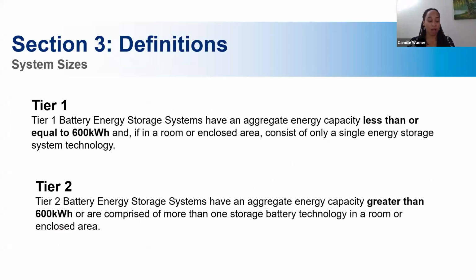For tier 1, let's jump into definitions. Tier 1 systems are defined as a BESS system with an aggregate or total energy capacity less than or equal to 600 kilowatt hours. If it's in a room or enclosed area like a garage, it can only consist of one energy system type, so only lithium ion. Tier 2 systems are greater than 600 kilowatt hours and/or can be comprised of more than one battery energy technology in a room or enclosed area.